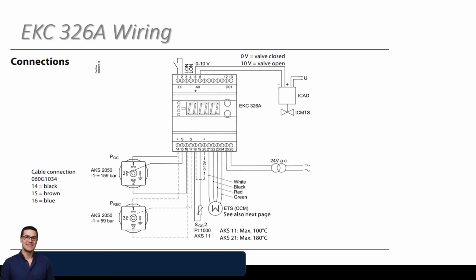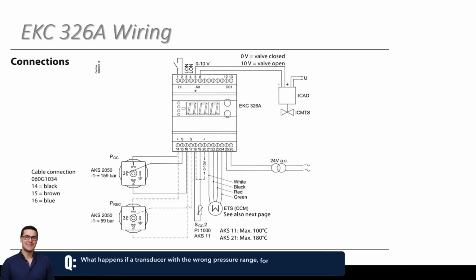Yeah. Always check pressure range. It doesn't matter what pressure transducer it is, because a lot of them look the same from all the different manufacturers, but the pressure range is different, right? So you have to check that and make sure it's the right range, because if you put the wrong range one in there, just say you put a 159 and a 59 bar one, it's going to not know where it's at at all. Like it's going to think it's in a different location. So what happens, just say if they do put, let's say 159 bar, the gas cooler one in a receiver one, what would happen to the controller?